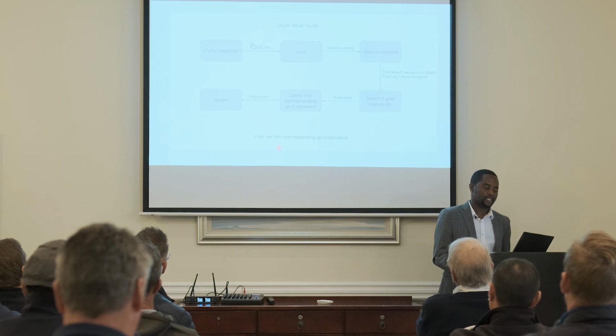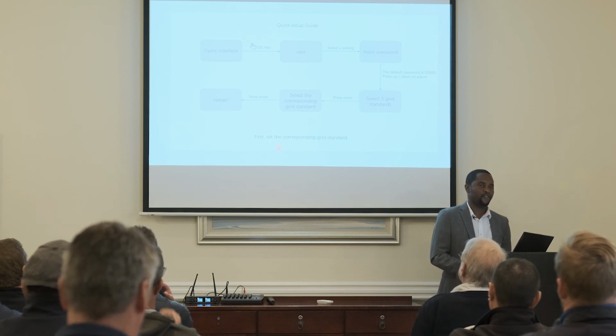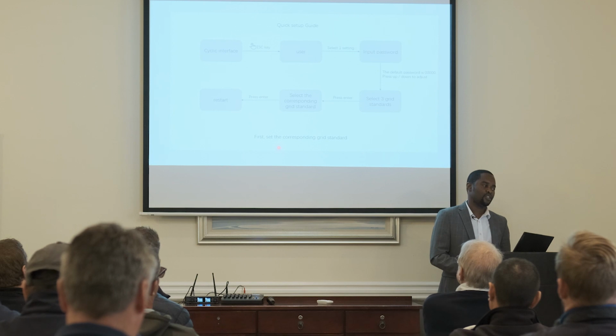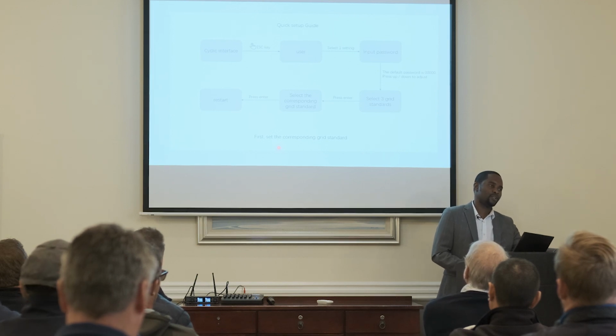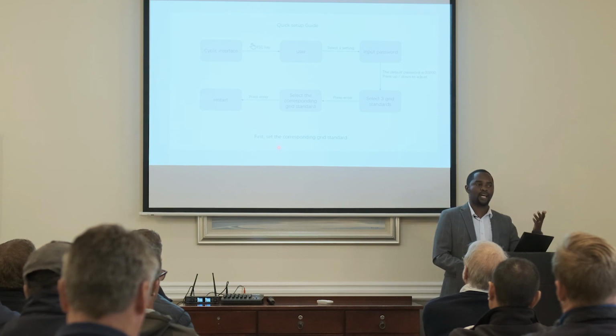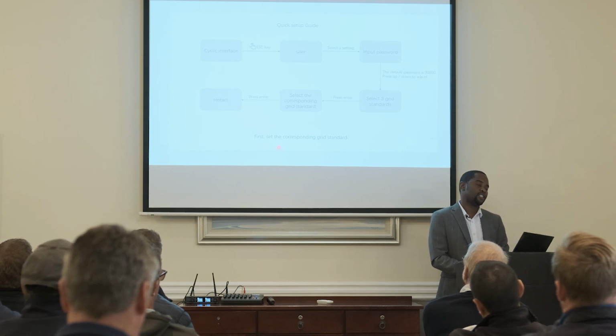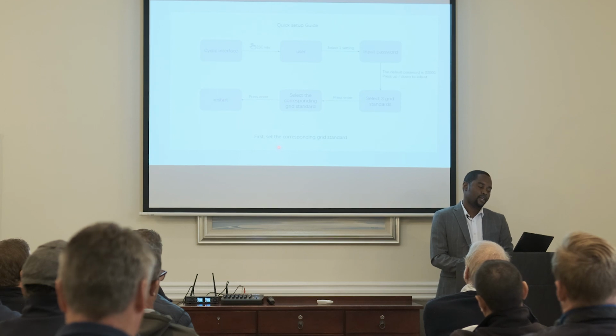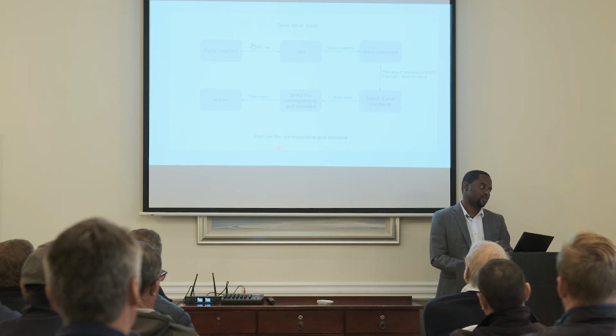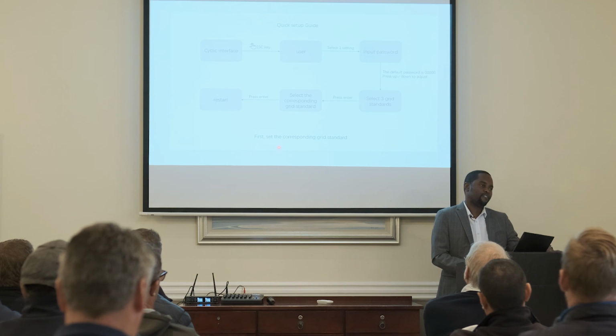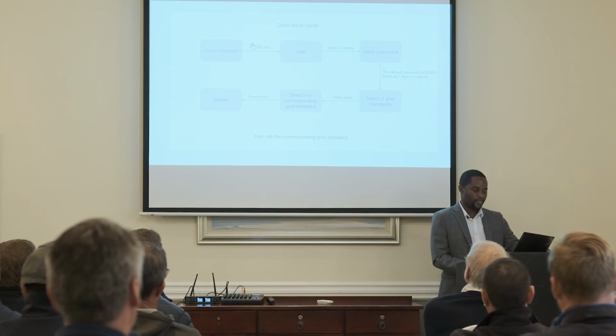So on the quick setup guide, these are just some of the scenarios that we have. You don't need to change a lot of stuff. This is the only inverter now that is by default already on lithium. So the moment you put that communication cable and you've got a lithium battery, it picks that battery automatically. What you need to change, obviously, is to customize your charge currents and your discharge currents. The charge is 25 amp by default, so you may need to put it a little bit higher. Then the discharge is on the size of the 5 kilowatt, so you can actually use it on 5 kilowatt without changing all that.